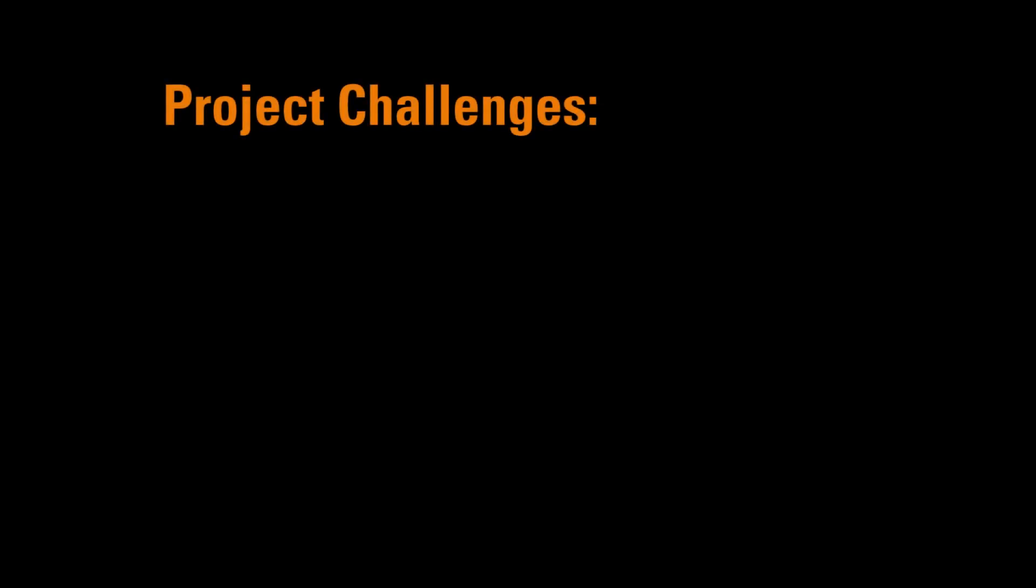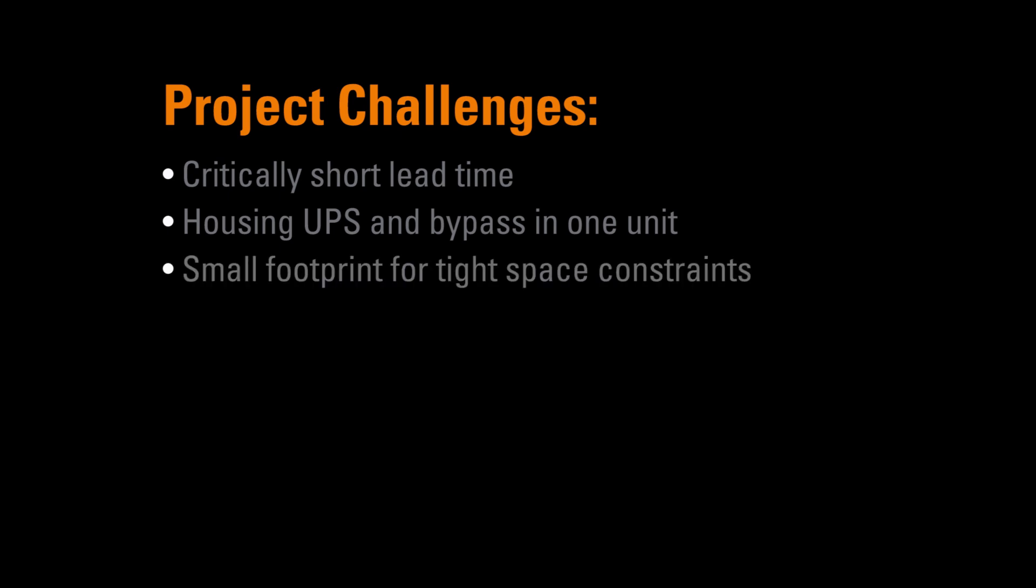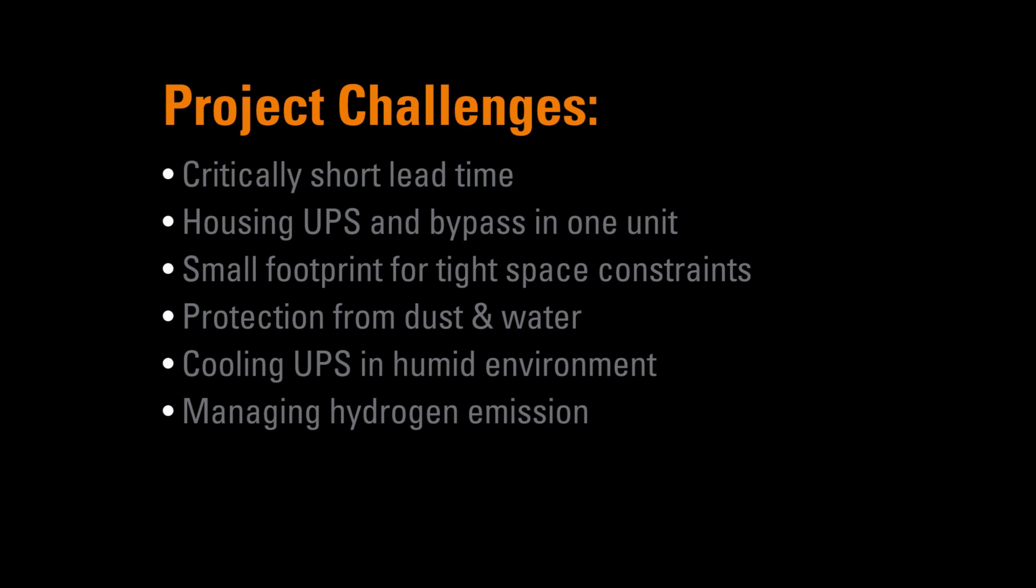The challenges we faced in creating the solution included the end customer's critically short lead time, housing the large UPS and maintenance bypass in one package, minimizing the footprint to meet the end customer's space constraints, protecting the internal equipment from dust and particulates in the air, as well as splashing or hose-directed water spray, cooling the UPS in Mississippi's humid environment, and managing possible hydrogen emission due to use of sealed lead-acid batteries.